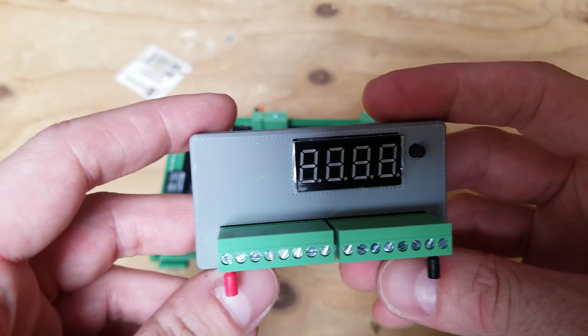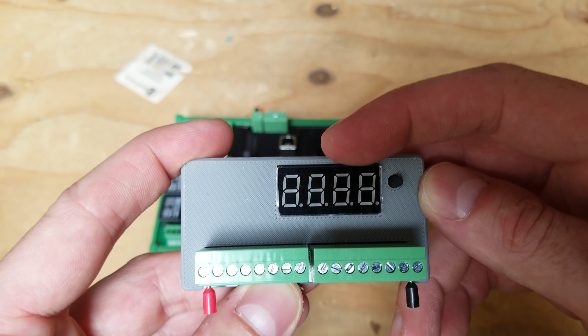The idea is we need to connect each one of these pins to this TestMon. Once all 14 are connected, we push the top right button, and this tells us whether our connection passes or fails. If it passes, it means all your wires are connected in the correct order and correct polarities, and then we can transfer the connector to the Watchmon 5 itself.